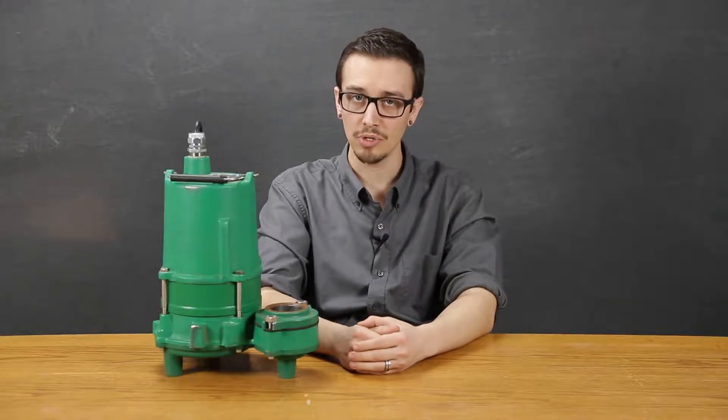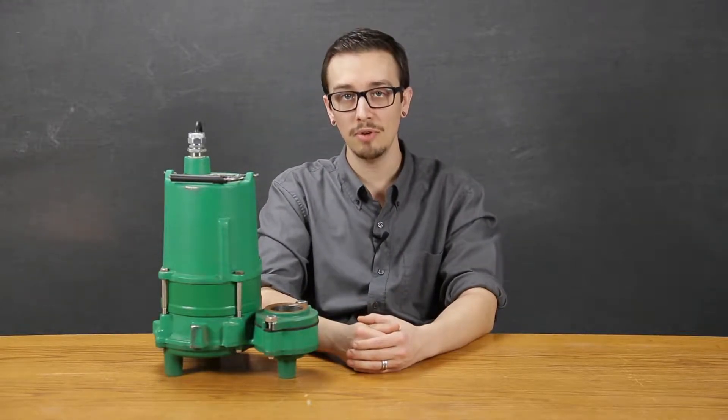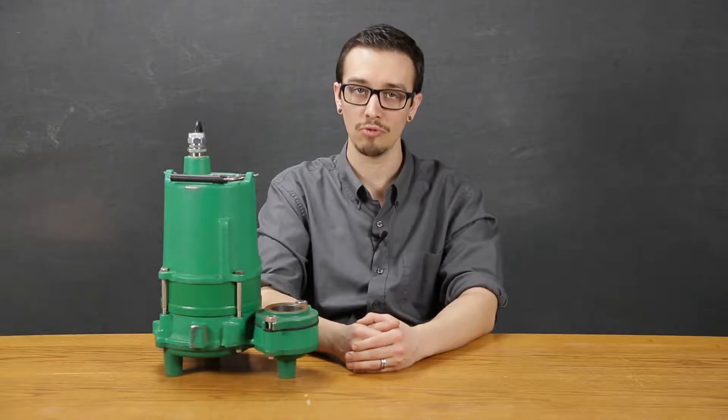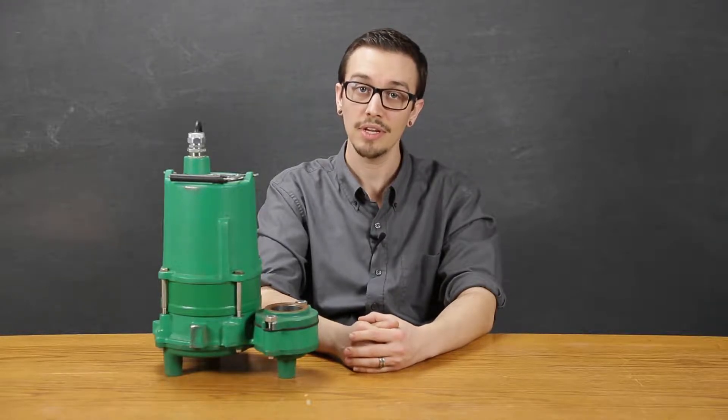The minimum sump diameter recommended for these pumps in a simplex configuration is 24 inches and 36 inches for duplex configurations. By maintaining this minimal sump diameter, we ensure that the equipment has enough room for proper operation and helps to eliminate cord entanglement issues.